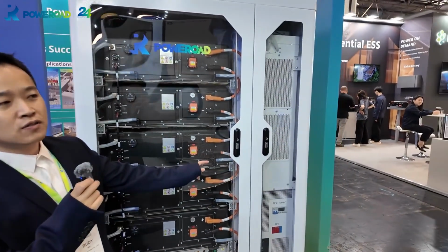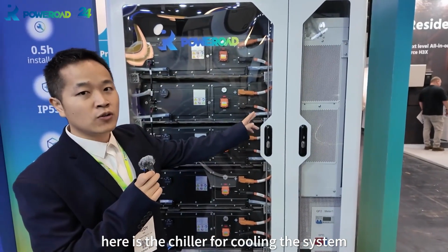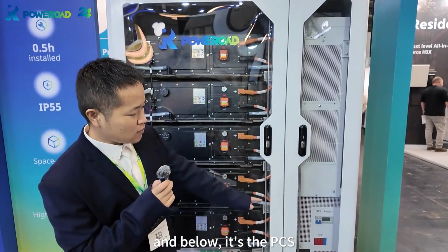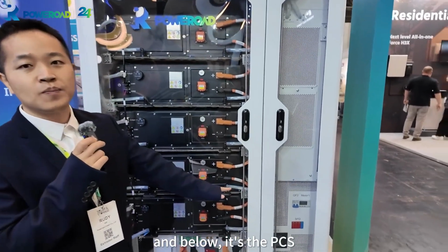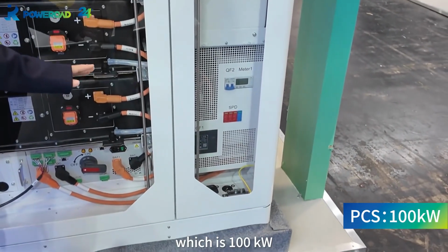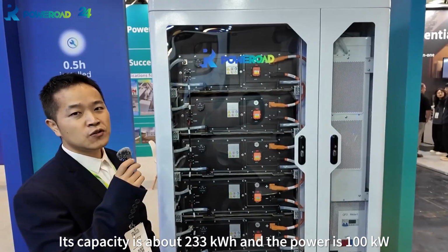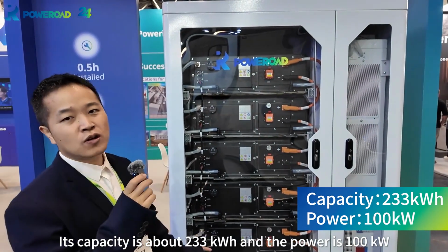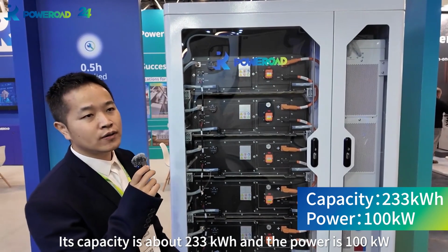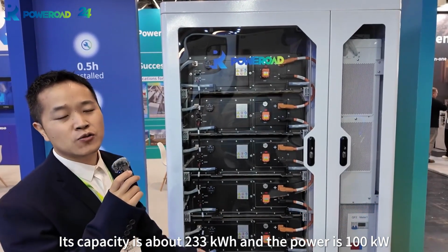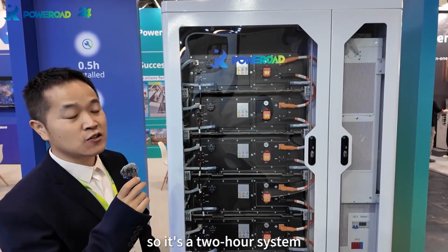On the right here is the chiller for cooling the system, and below is the PCS, which is 100 kilowatt. So its capacity is about 233 kilowatt hours, and the power is 100. So it's a 2-hour system.